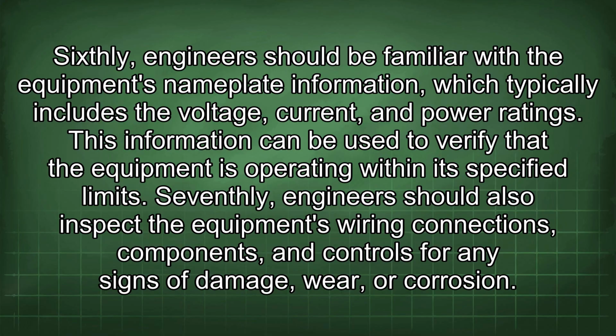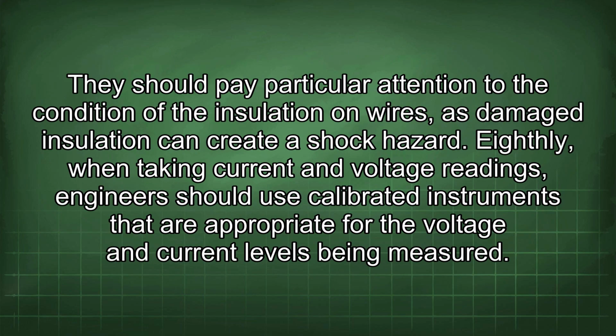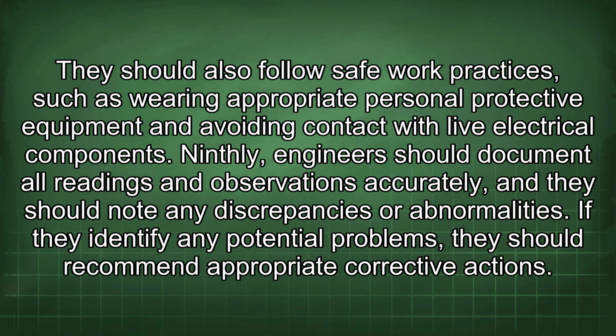Seventhly, engineers should also inspect the equipment's wiring connections, components, and controls for any signs of damage, wear, or corrosion. They should pay particular attention to the condition of the insulation on wires, as damaged insulation can create a shock hazard. Eighthly, when taking current and voltage readings, engineers should use calibrated instruments that are appropriate for the voltage and current levels being measured. They should also follow safe work practices, such as wearing appropriate personal protective equipment and avoiding contact with live electrical components.